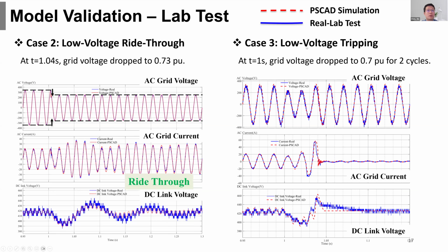Case three is we continue to do the low voltage tripping testing. If we keep dropping the grid side voltage to 0.7 per unit for 2 cycles, you can see from the first figure, the AC side voltage decreased from 1 per unit to 0.7 per unit for 2 cycles. And the second figure is the corresponding AC grid currents. The red curve is the simulation results, and the blue curve is the real lab testing. In this case, we can see because of the voltage drop, there is a current increase. And this current increase is over the threshold for protection. So we have a tripping event here. You can see that after this tripping, the AC grid current becomes zero. This means the facility is tripped from the grid. And the last one is the DC link voltage.